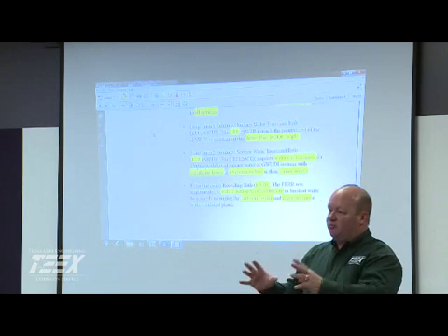I wonder about membrane integrity. If you have concentrated crypto in there, and you have a breach in your membrane, and you don't have any kind of physical filtration afterward. I can't remember all the tests that we had them doing, but I think TOC was one, THM, HAAs, pH, alkalinity.